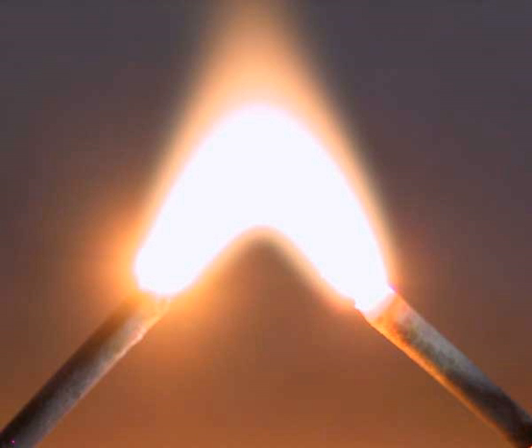An electric arc differs from a glow discharge in that the current density is quite high, and the voltage drop within the arc is low. At the cathode, the current density can be as high as 1 megaampere per square centimeter. An electric arc has a nonlinear relationship between current and voltage. Once the arc is established, either by progression from a glow discharge or by momentarily touching the electrodes then separating them, increased current results in a lower voltage between the arc terminals.